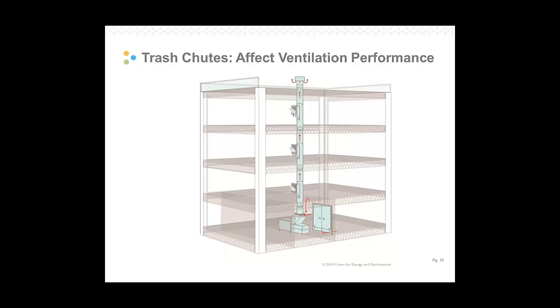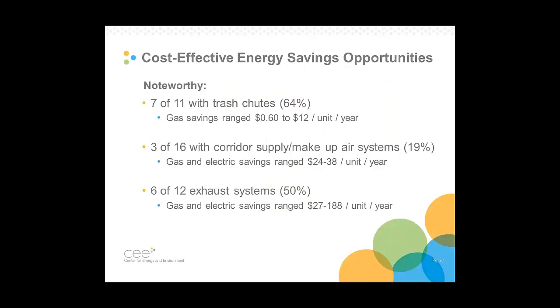This research also looked at trash chutes. Trash chutes can affect ventilation performance. The purpose of a trash chute is to allow access for residents to drop trash into the dumpster from any floor in the building. Building air connected with this trash chute can cause odor problems coming from the trash chute. It also can draw excessive heated air up this chute. You can see that there's a passive termination here at the rooftop, and if this trash chute's connected extensively to the building air, there can be a lot of airflow via stack effect out the trash chute, so it can draw heated air out. It can be an energy cost. So odors and energy cost. I'll go into that a little more later.